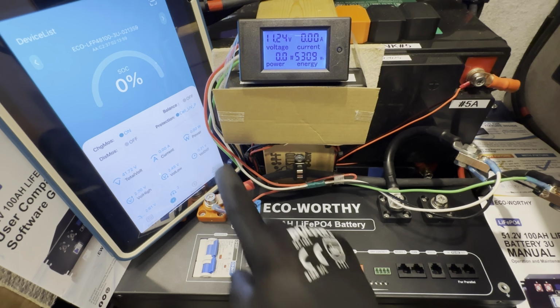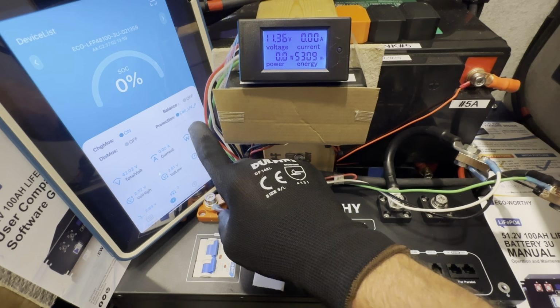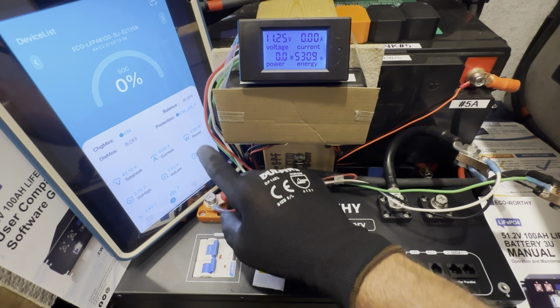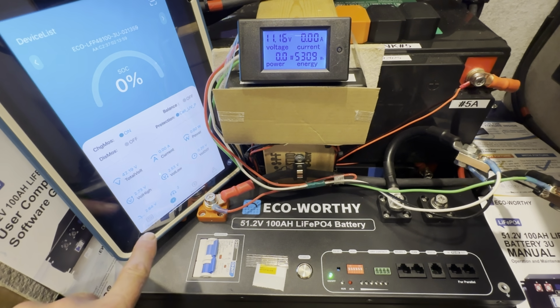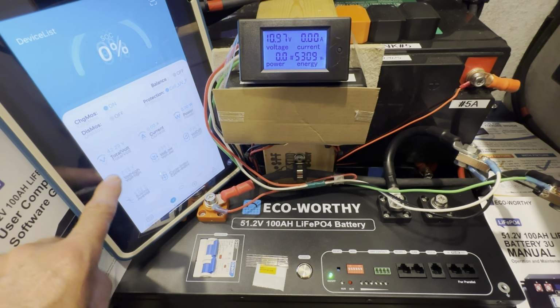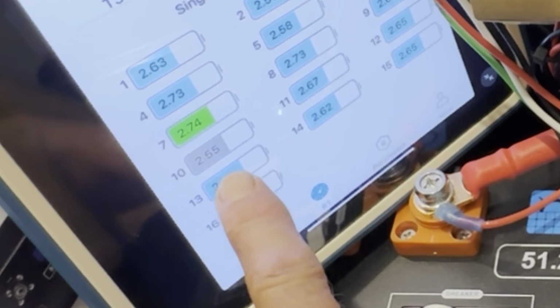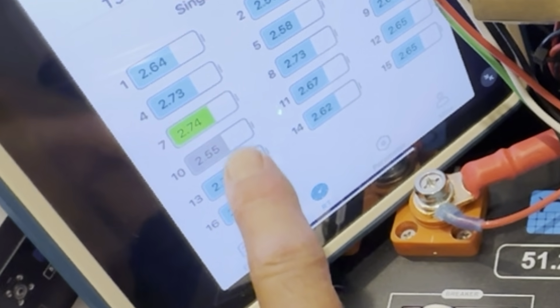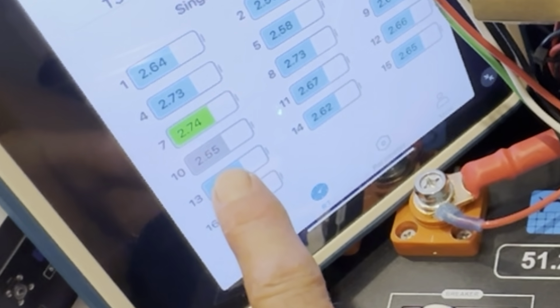All right, the BMS shut off on the battery. I thought it was the inverter, but we'll look right here - we see cell under voltage protection. So one cell went below its protocol parameter in the BMS. Let's see which one it is - looks like this cell right here, number 10, that's got the lowest voltage of the bunch by quite a margin, 2.55 volts.